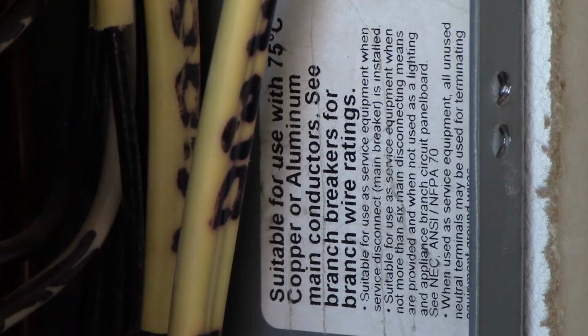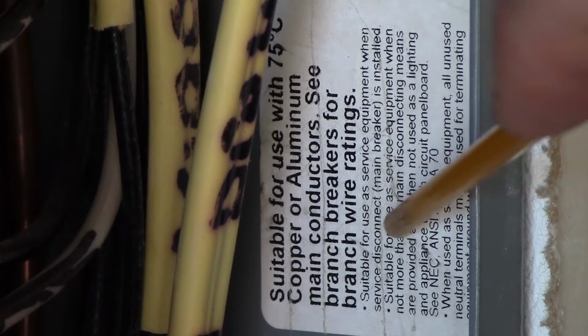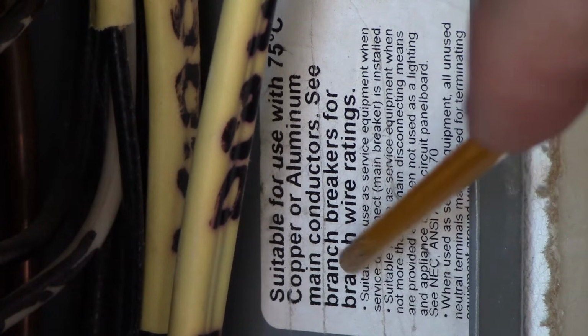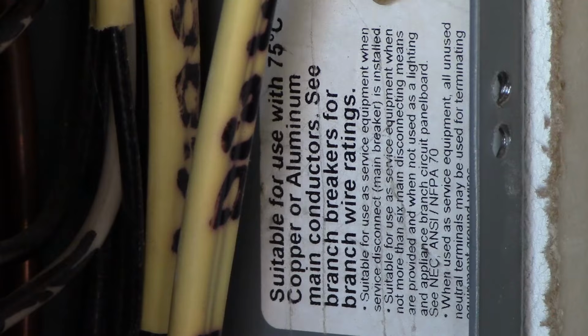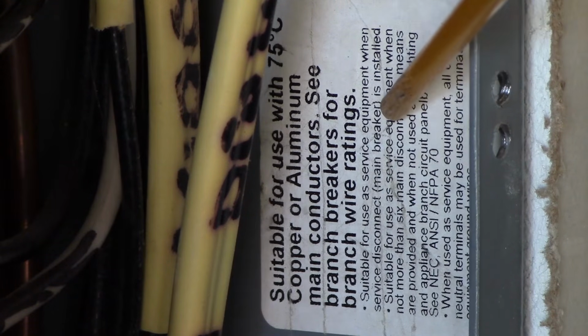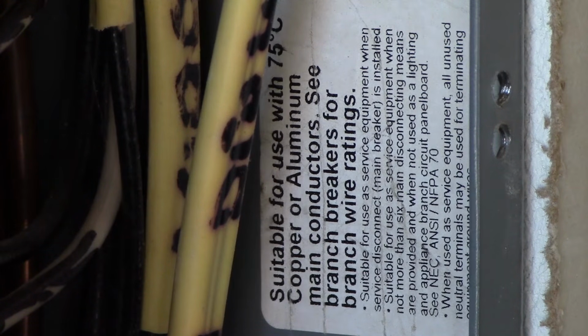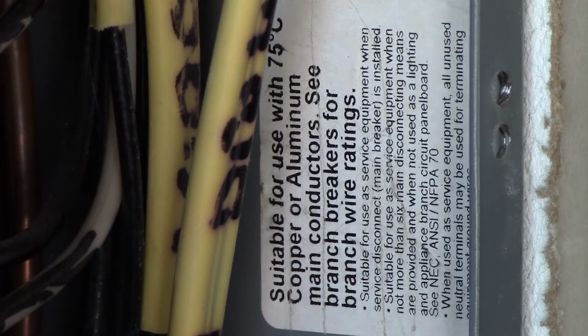The one thing I want to point out in here is it says right here that this panel is suitable for use as service equipment when the service disconnecting means, that's the main breaker, is installed. And of course, we have a main breaker. We are using it as service equipment. So that's the statement that tells us that.